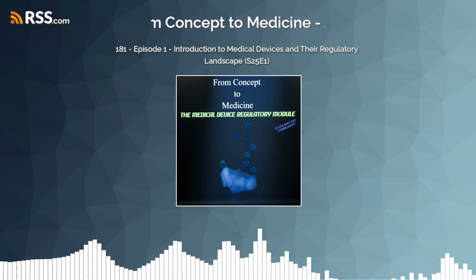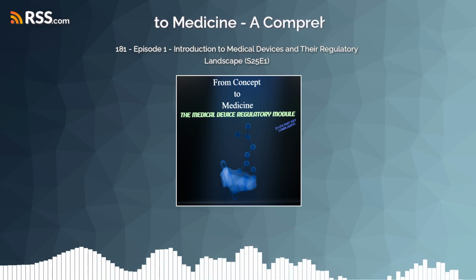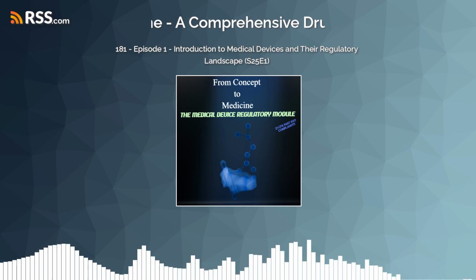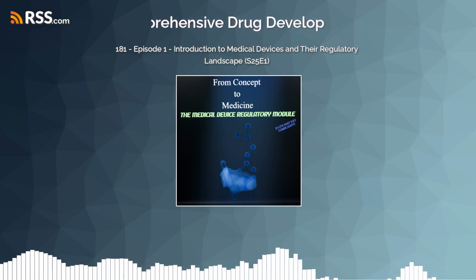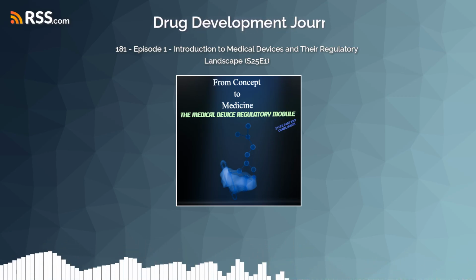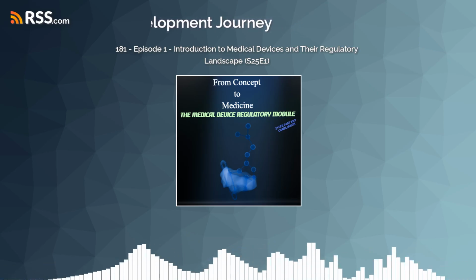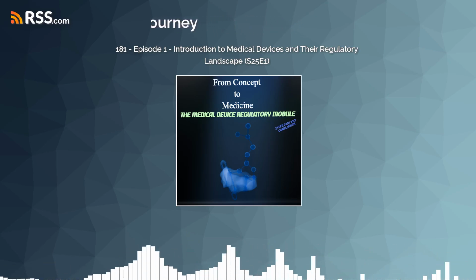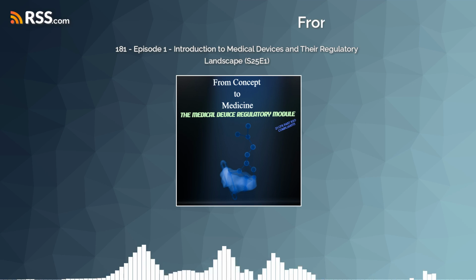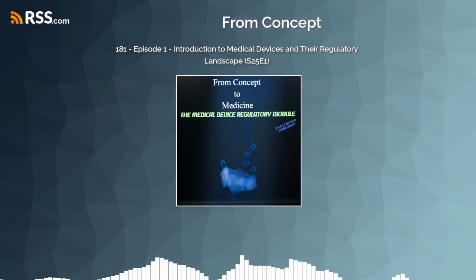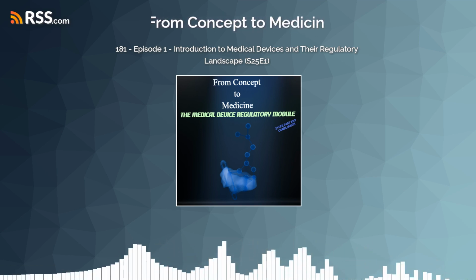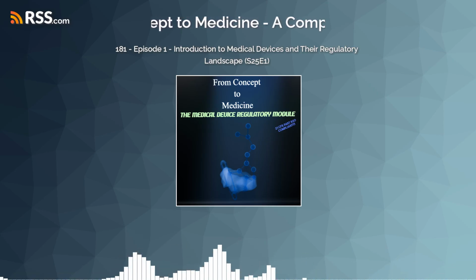So once the FDA has this definition, how do they categorize devices? I imagine not all devices pose the same level of risk, right? And that must fundamentally change the whole process. You've absolutely hit on a critical point. Devices are sorted into three main classes, Class 1, 2, and 3, and it's all based on their potential risk to patients and the level of control needed to ensure safety and effectiveness.